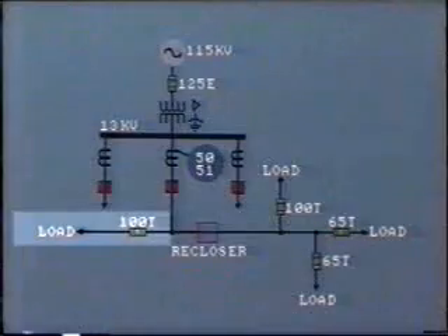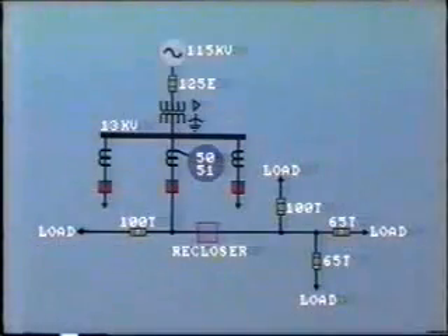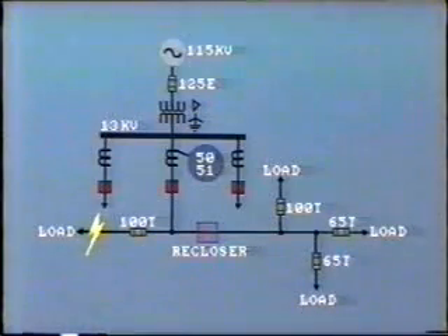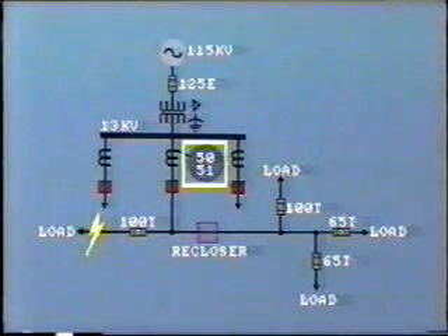This particular branch has no recloser, so a temporary fault out on this circuit would cause the instantaneous overcurrent relay to open the feeder breaker. After a time delay, a reclosing relay would cause the breaker to reclose. After this one reclosing, the instantaneous overcurrent relay is prevented from operating again until a timer times out, usually several seconds. If the fault is permanent and remains on, then the fuse will operate to clear the circuit.